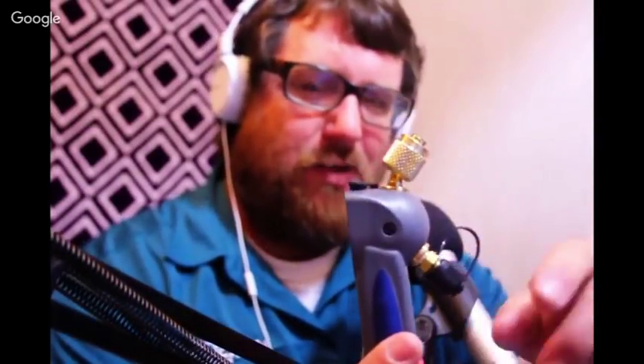So I'm going to open things up here. Of course, you have the instructions — who needs that, right? I'm just kidding, read the instructions. We have pressure probes, and the cool thing about these pressure probes is they're really durable feeling. You have a little band here to indicate if it's high side or low side, and also a pass-through right here so you can actually charge when the port's on there, or recover, or whatever you want to do. There is a little mini USB.